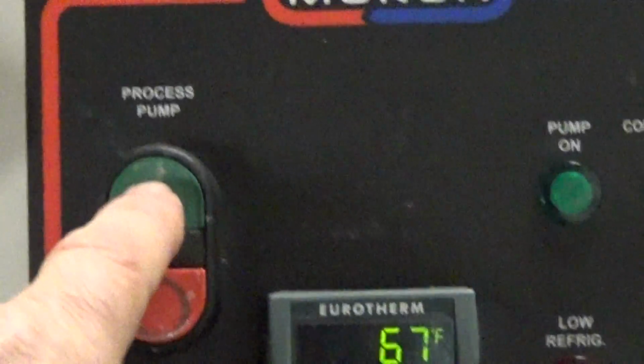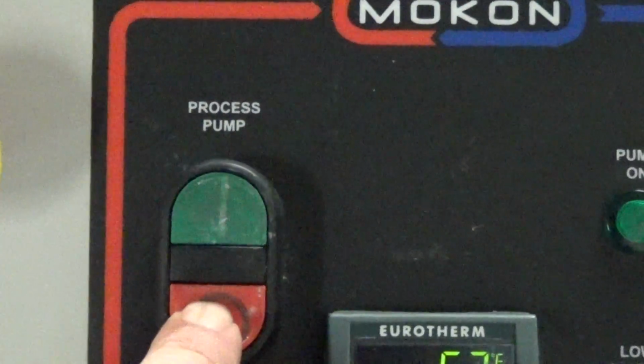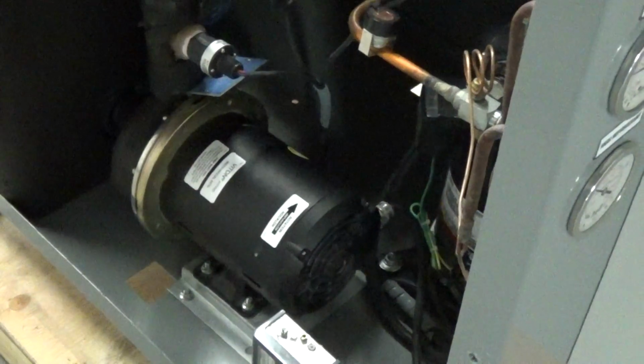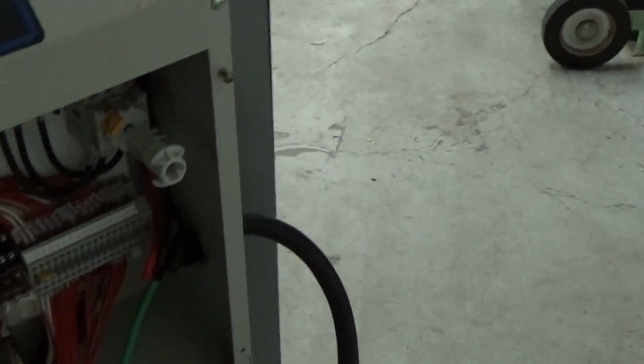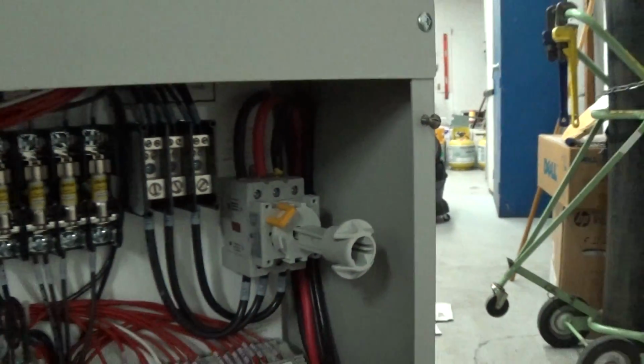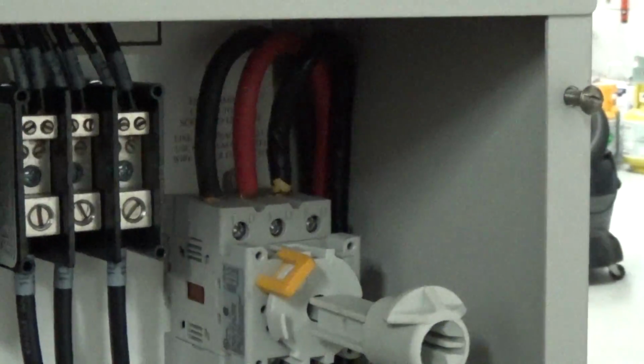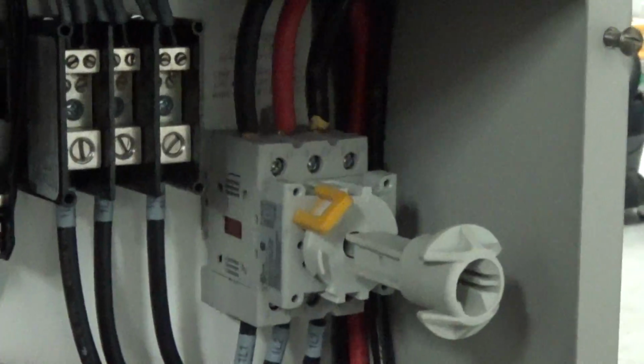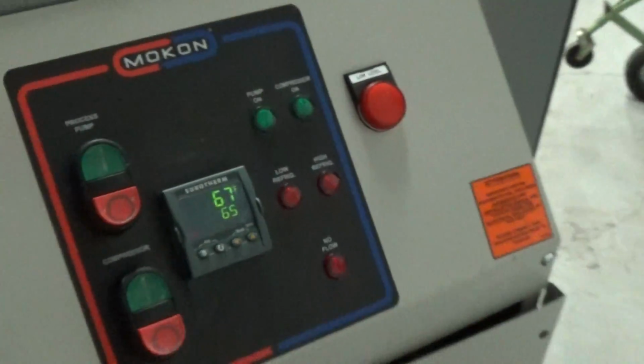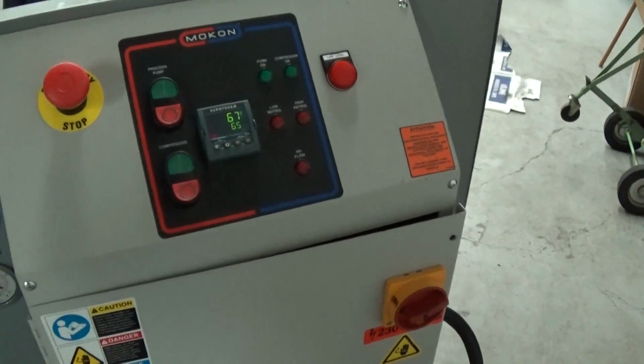And in this case here, you don't have to bump a contactor. You just have to bump it there to make sure. If it's going in the wrong direction on startup, first you want to disconnect your power, and you'll want to change your main incoming power here, not the pump power, but your main incoming power, okay? And obviously we've already been running this and already have it working.